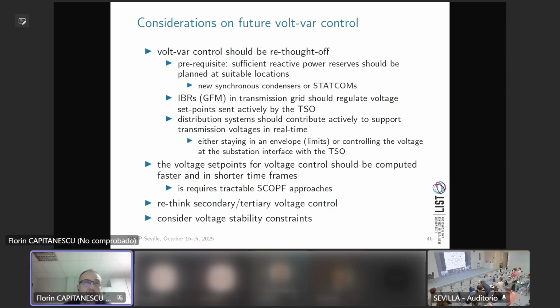If you look at converters, since they are already in the field and were at the beginning meant only to produce active power, you can see that in absorption they are only at 20%. So you see, that's the difference. In production they can go to 60%. They are amazing, they can do very fast and amazing things with it. But physically, the amount of reactive power they can produce is smaller, much smaller than with a synchronous generator. That was my main point.